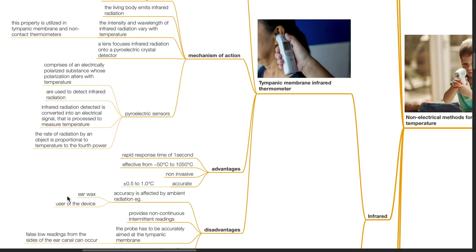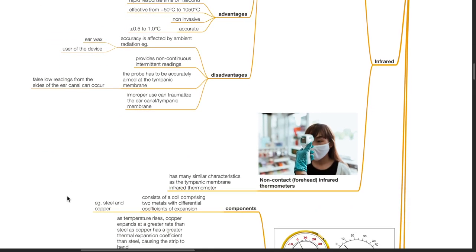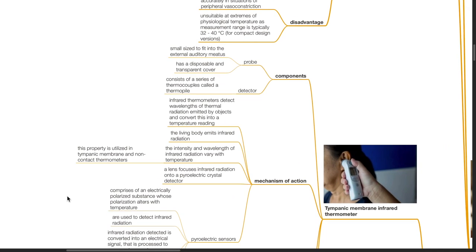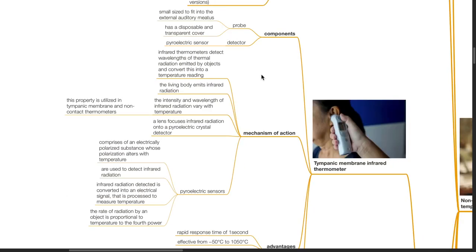Infrared thermometers may be tympanic membrane or non-contact forehead infrared thermometers. A probe, small enough to fit the external auditory meatus, has a disposable transparent cover. The detector is a pyroelectric sensor. Infrared thermometers detect wavelengths of thermal radiation emitted by objects and convert this into a temperature reading. The living body emits infrared radiation; the intensity and wavelength vary with temperature. A lens focuses infrared radiation onto a pyroelectric sensor, which comprises an electrically polarized substance whose polarization alters with temperature. Infrared radiation detected is converted into an electrical signal that is processed to measure temperature.